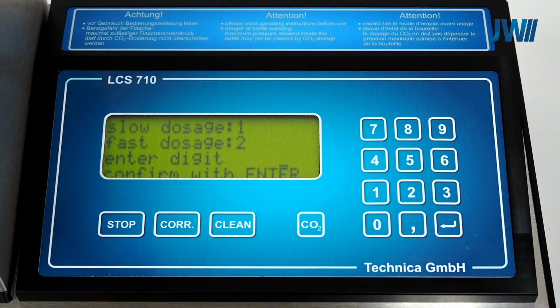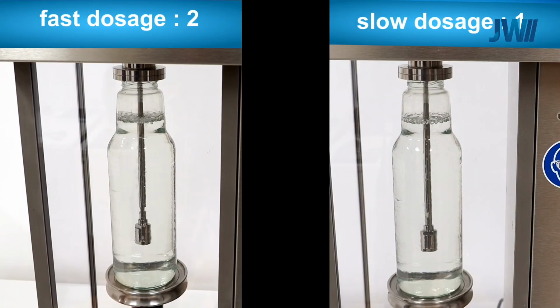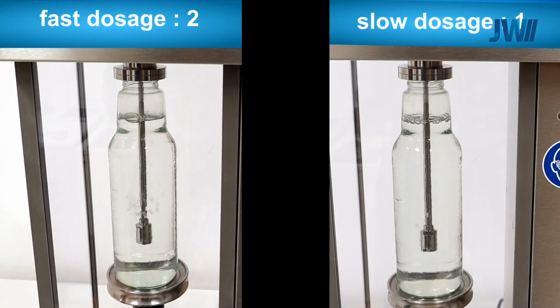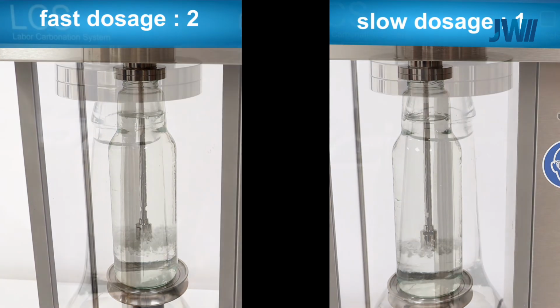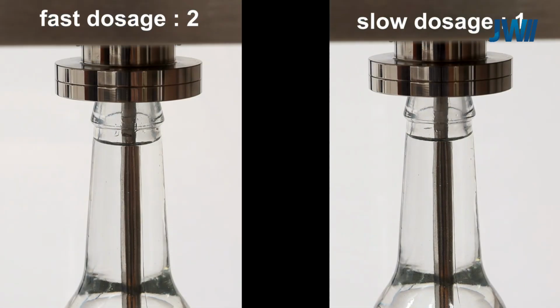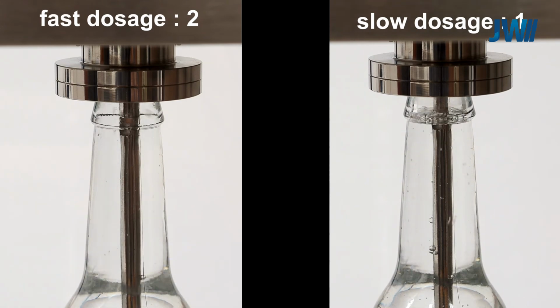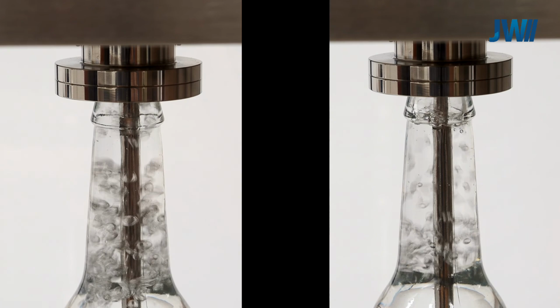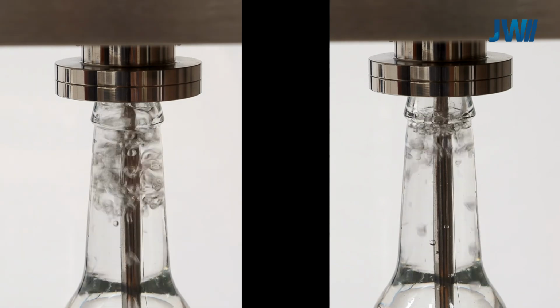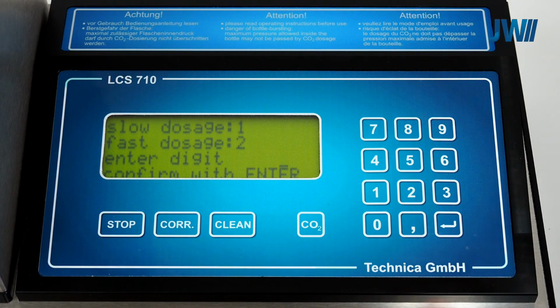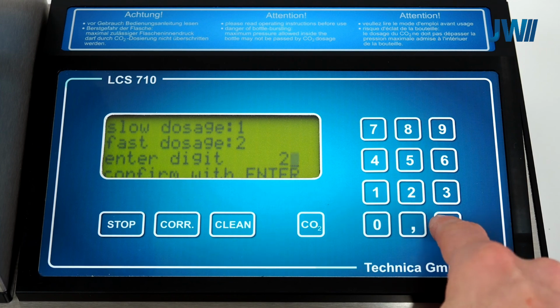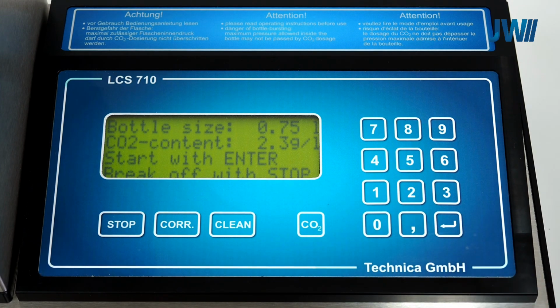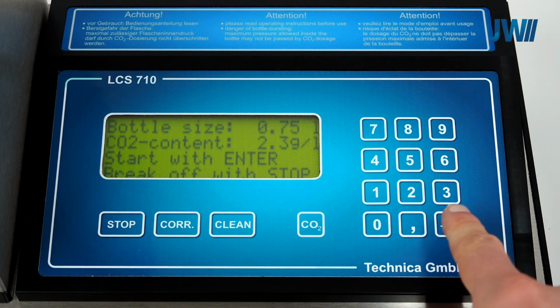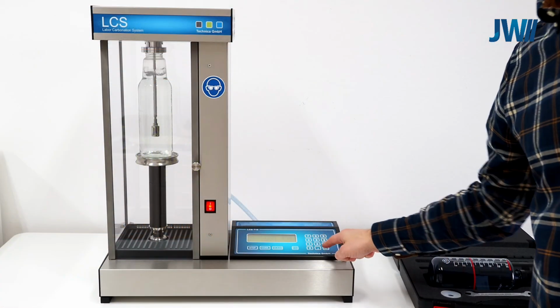The final parameter is the dosing speed. Selecting fast doses a larger amount of gas per burst, speeding up the process. For small bottles or bottles with little headspace, choose slow to minimize liquid entering the probe head or dosing system. While the device can handle this, it can create a mess. Press Enter to start the dosing process.